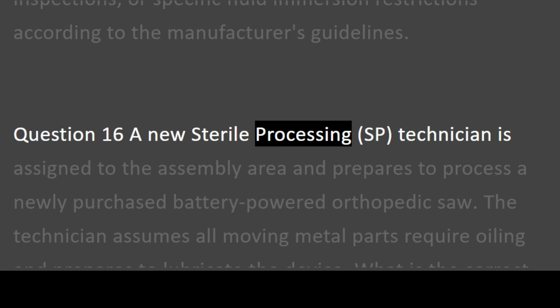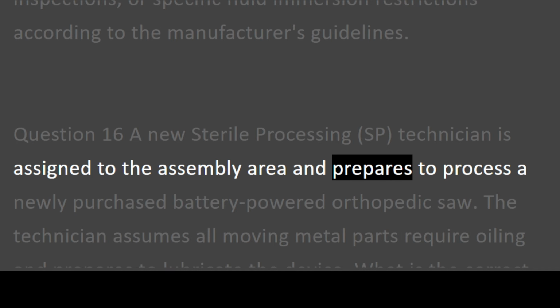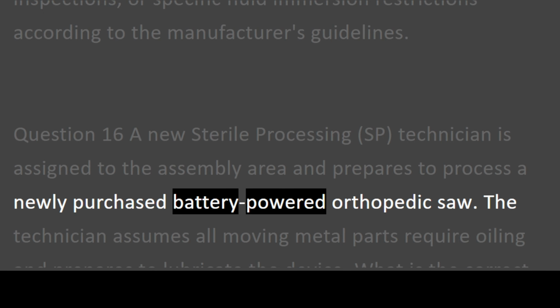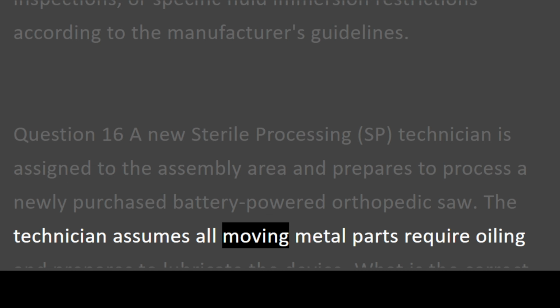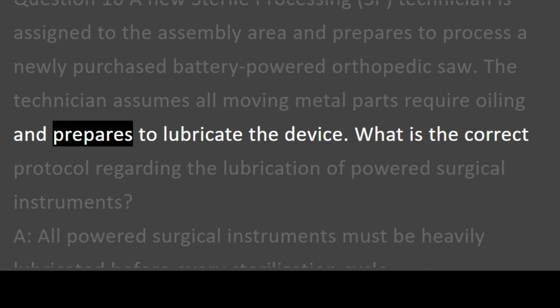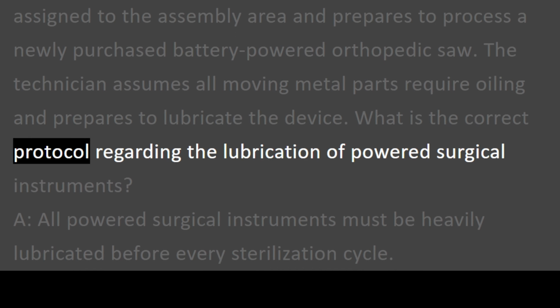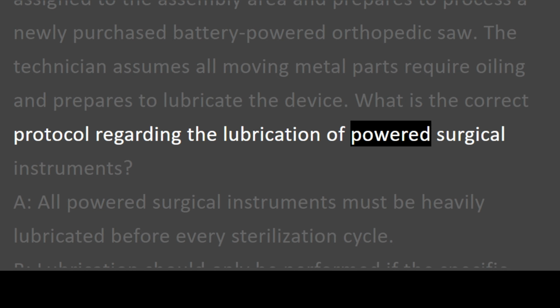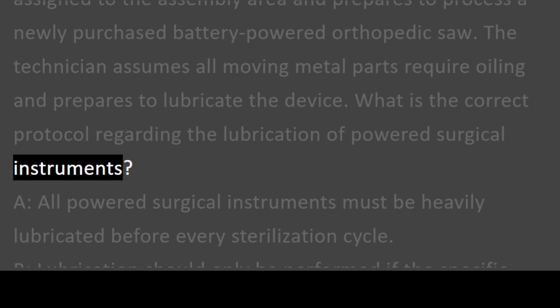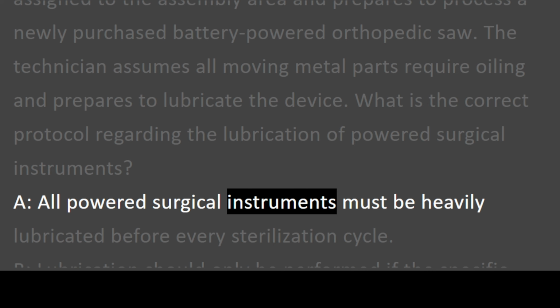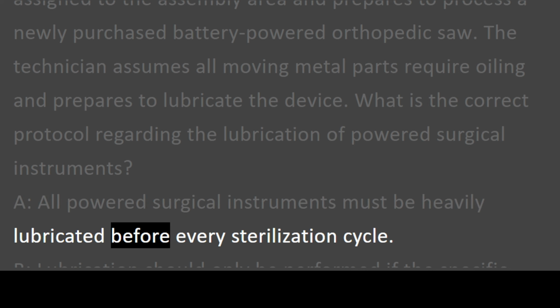A new sterile processing (SP) technician is assigned to the assembly area and prepares to process a newly purchased battery-powered orthopedic saw. The technician assumes all moving metal parts require oiling and prepares to lubricate the device. What is the correct protocol regarding the lubrication of powered surgical instruments? A. All powered surgical instruments must be heavily lubricated before every sterilization cycle.